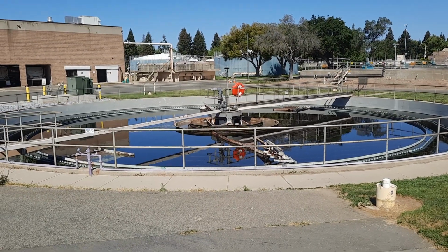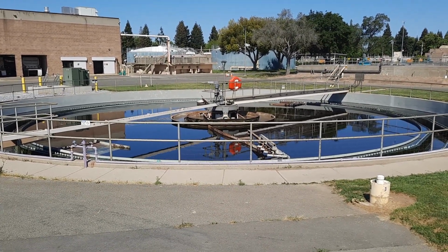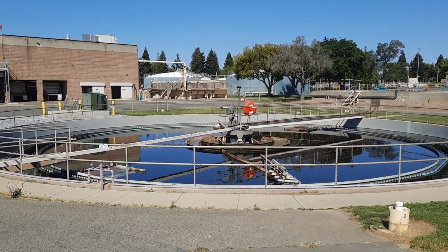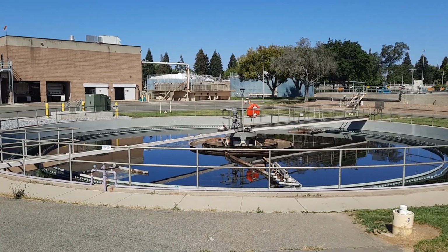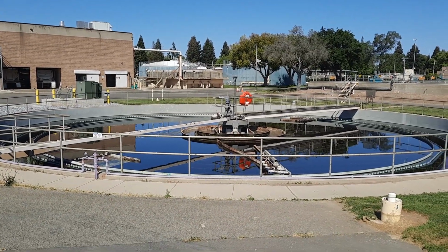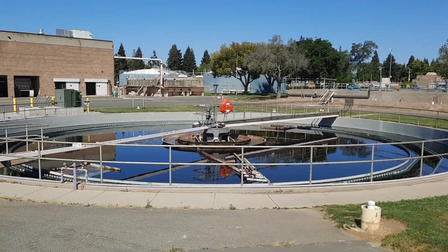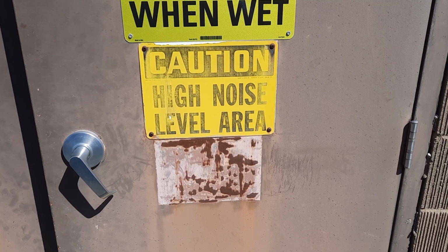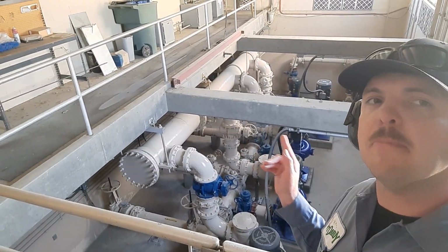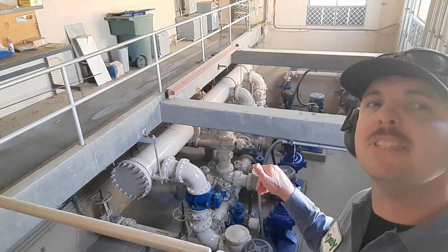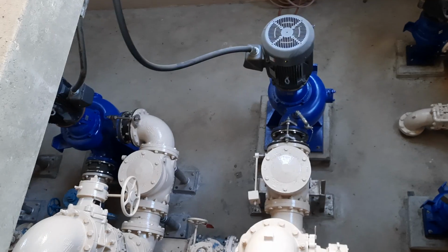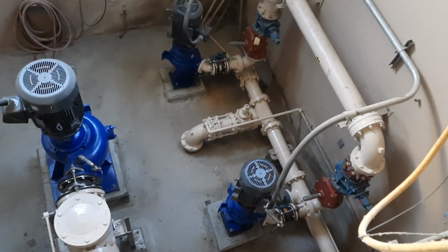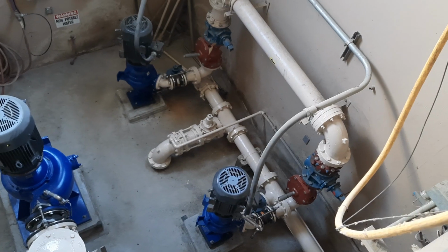Just like with a primary clarifier, we're using the same principle here. The secondary influent flows from the center and is slowed down as it flows to the outside, and this allows what's now living bacteria to settle at the bottom of this clarifier. The bugs from the bottom of the secondary clarifiers are pumped by these pumps back to the beginning of the biological process. These big pumps return sludge back to the biological process, and these smaller ones are going to waste the sludge out of the system.